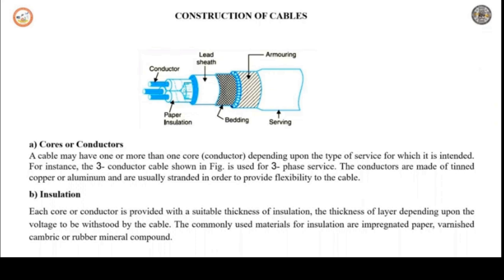First is the conductor or core. This section consists of a single conductor or more than one conductor. The conductors are also called as cores. A cable with three conductors is called a three core cable. The conductors used are aluminum or annealed copper, and they are stranded conductors in order to provide flexibility to the cable.